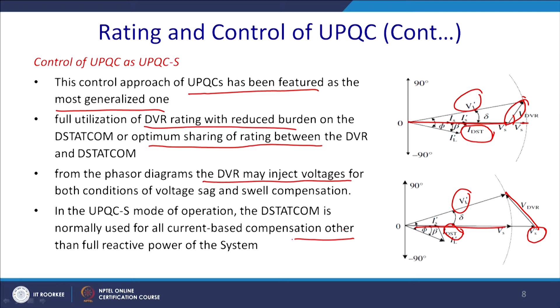In the UPQC S mode of operation, the D-STATCOM is normally used for current based compensation other than full reactive power of the system. In this case, the DVR injects voltage in series with the AC mains and the load end at a predetermined phase angle with the PCC. So, ultimately the tasks of the DVR and the D-STATCOM are segregated, and ultimately they will decide which angle and which phase the voltage and current are to be injected. They need both active power, as we have seen that it is injecting neither in quadrature nor in phase. So, some portion of the active power is also required, and the reactive power, both from the DVR.